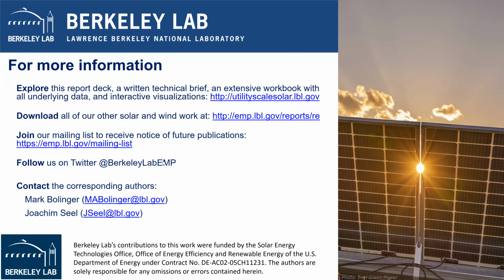Okay, I'll take another one. Someone asked whether the degradation measure that I showed, the 1.2% per year performance decline rate, includes project downtime, and the answer is yes, it does. As I was trying to explain, we don't have high enough resolution data to really filter out downtime events. So yeah, it's definitely an imperfect measure that might be considered sort of all inclusive of everything that could possibly go wrong to your plant.